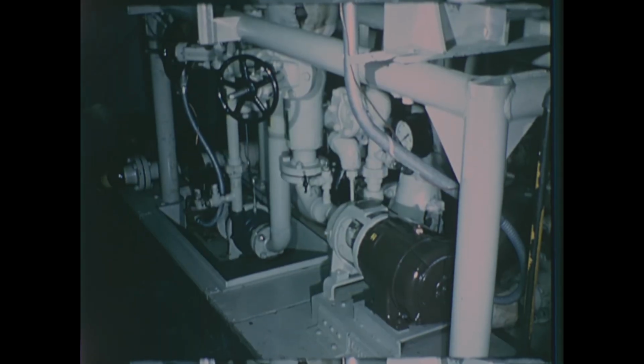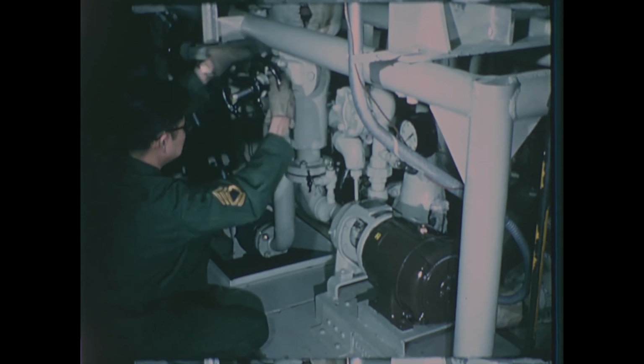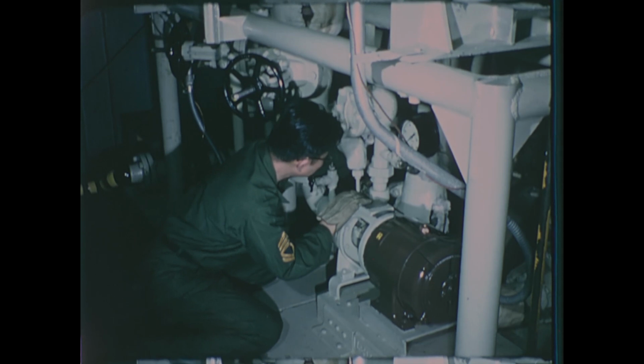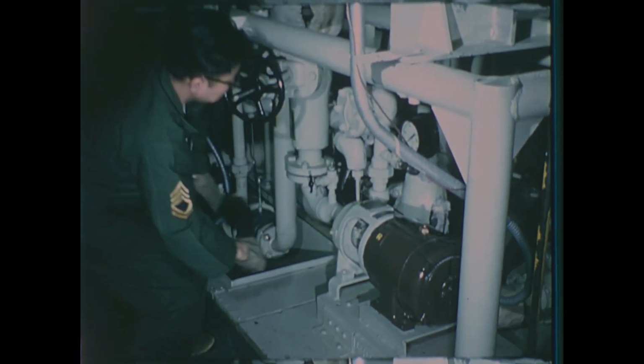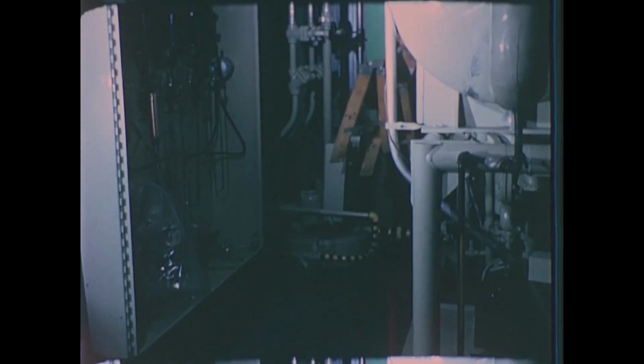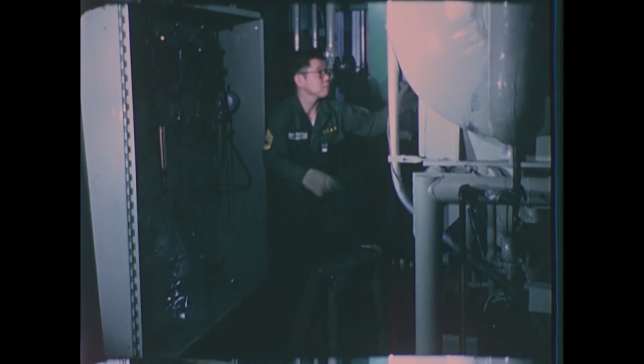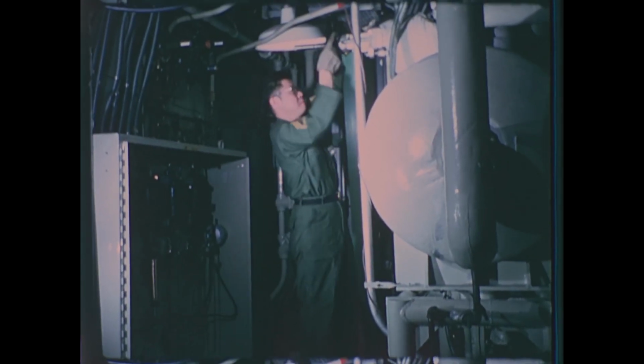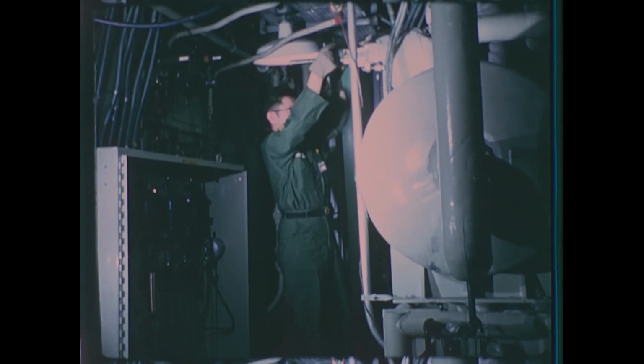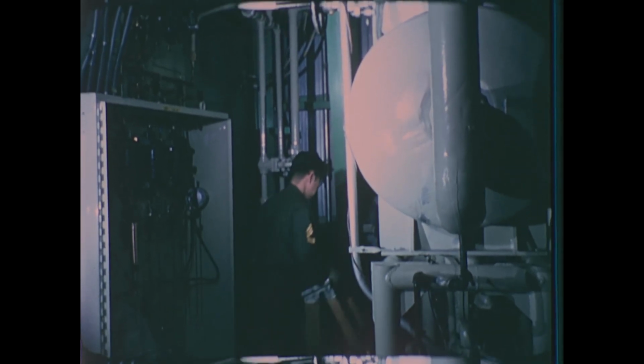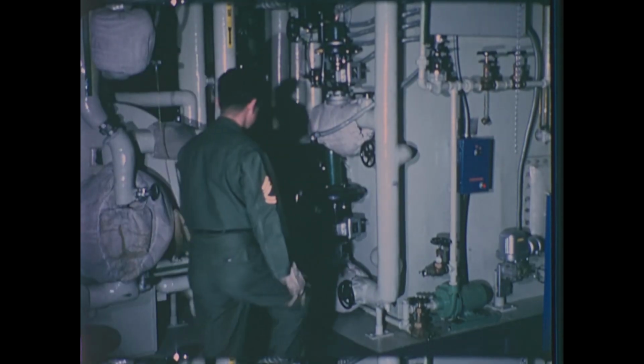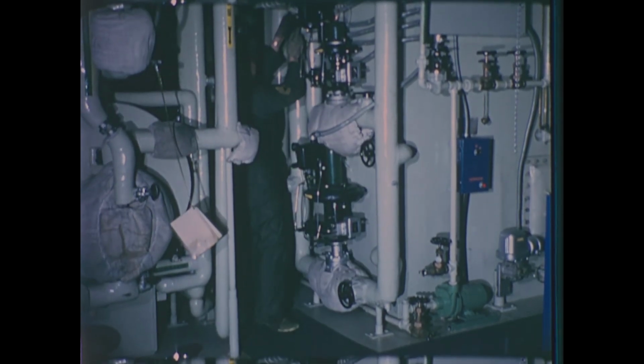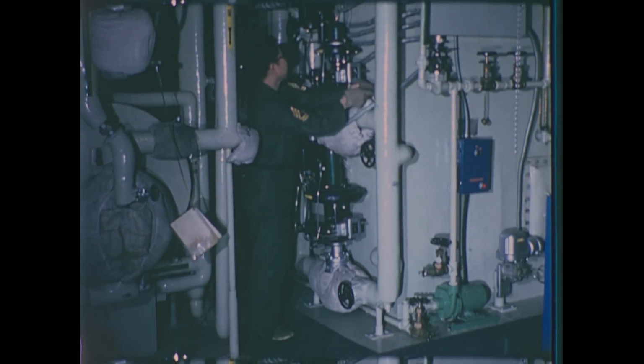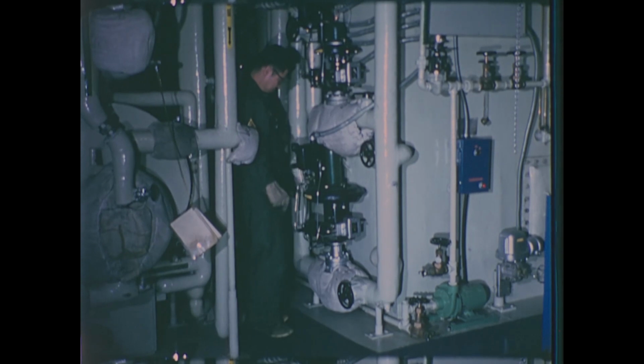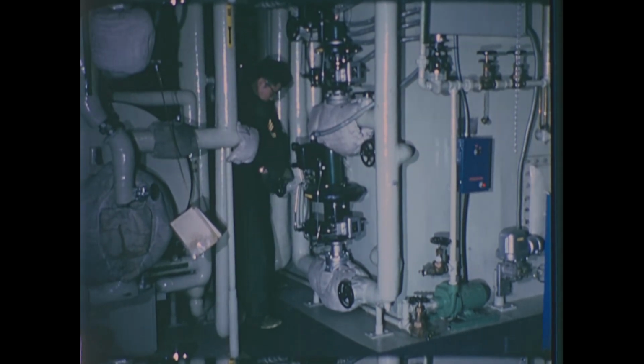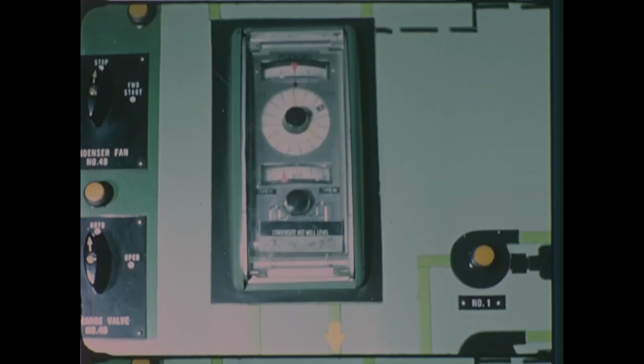The equipment operator readies the condensate system for operation, following the steps in the operating manual. Here he checks the condensate pump valve for proper lineup. He checks the valve from the hot well vent line to the turbine exhaust line for proper position. Another valve lineup. The hot well high-level controller, and the low-level controller. During operation, the predetermined level will be maintained by controllers at the console, functioning in the automatic setting.